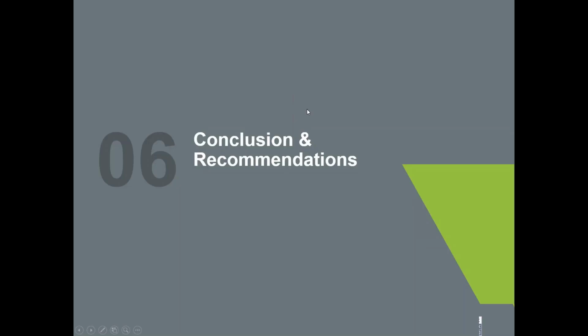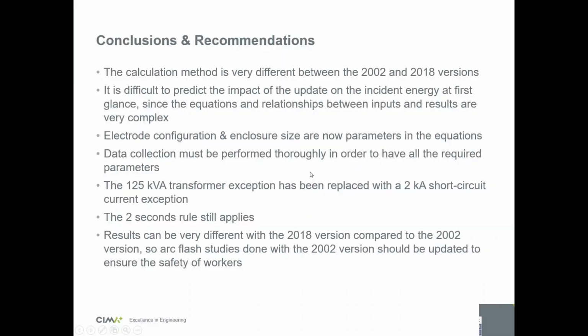So let's finish with some conclusions and recommendations. The calculation method, as you can see, is very different between the 2002 and 2018 versions. It's difficult at first glance to predict the impact of the update on the incident energy because the equations are very complex. The electrode configurations and enclosure size are parameters in the equations now. You need to go much further down in the distribution to consider everything with the new standards. The 125 kVA exception has been replaced, so you need to go down to around 30 kVA transformers. The 2-second rule still applies, and the results are very different, as you could see on the curves. So I recommend that your arc flash studies be updated to the new version to ensure the safety of the workers.